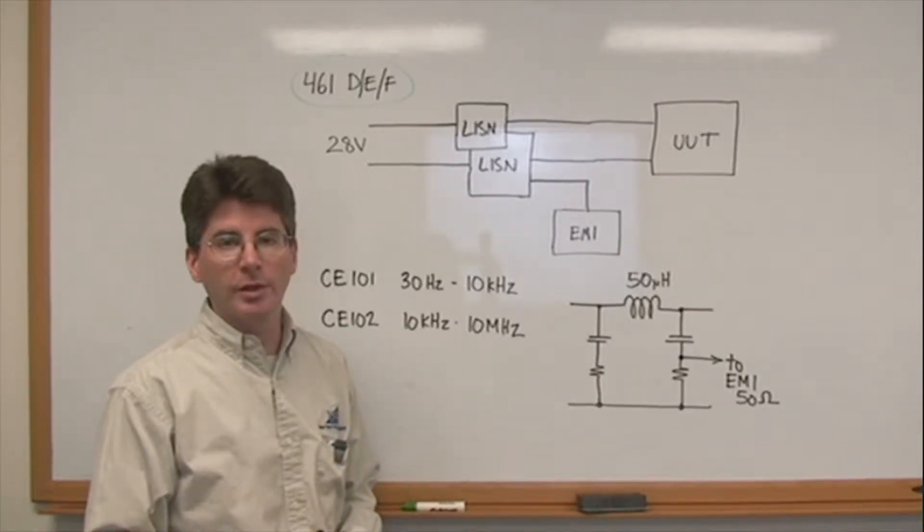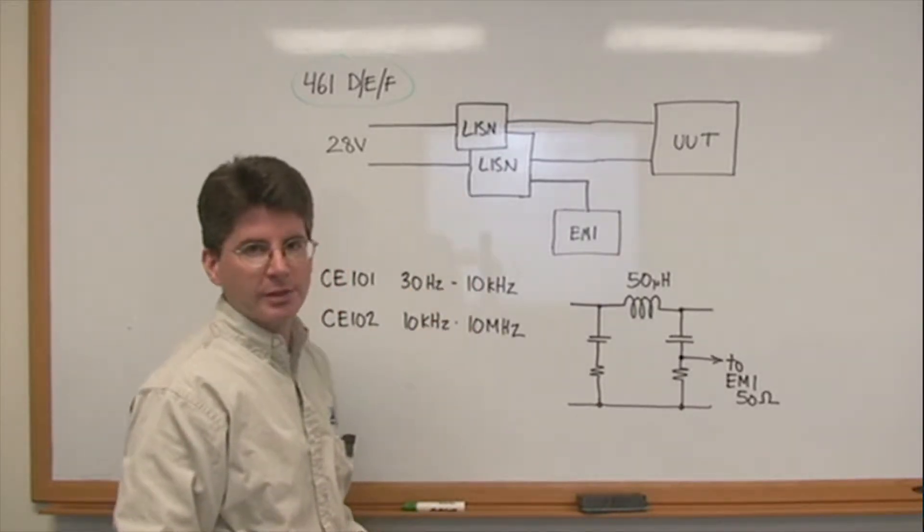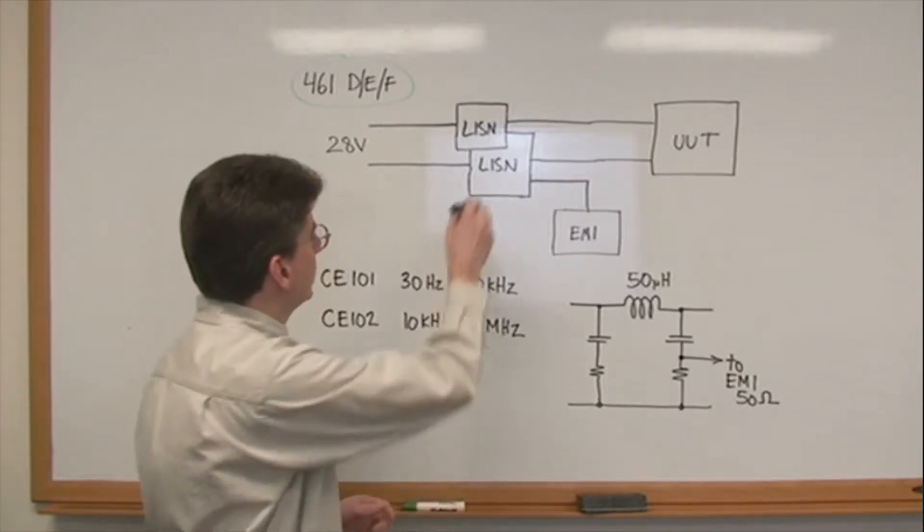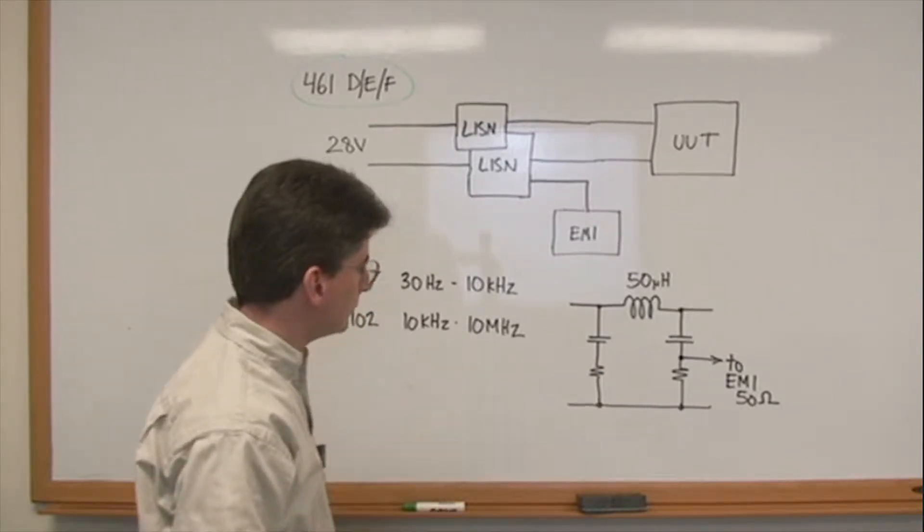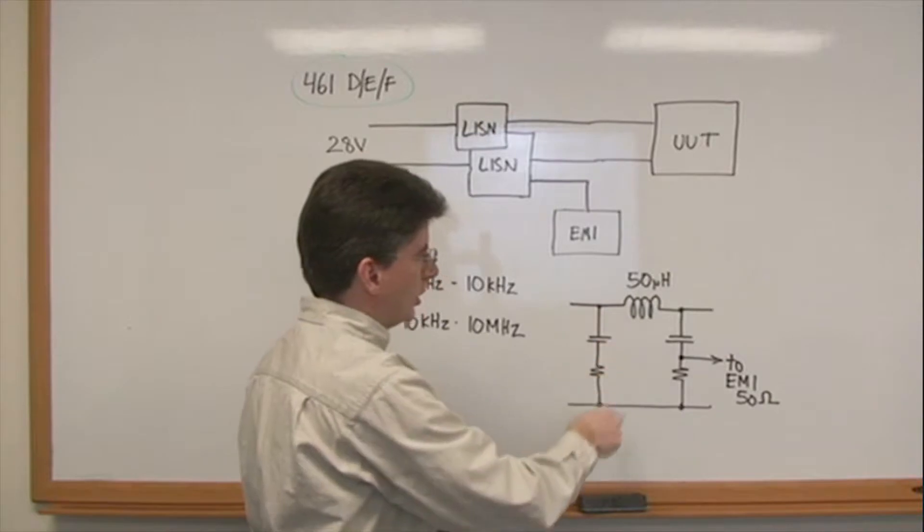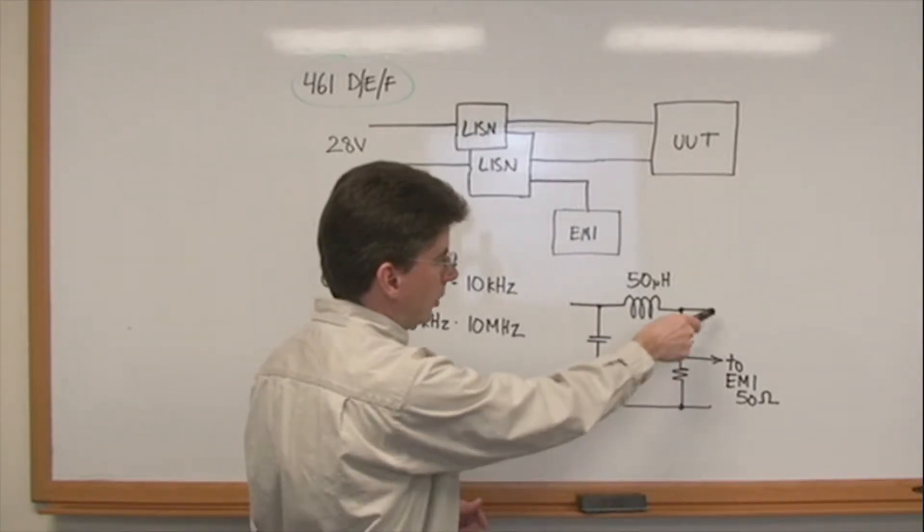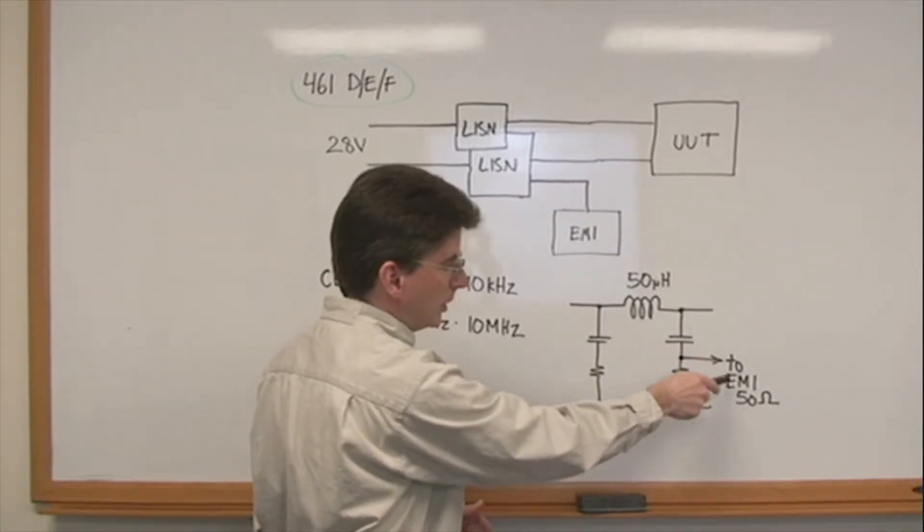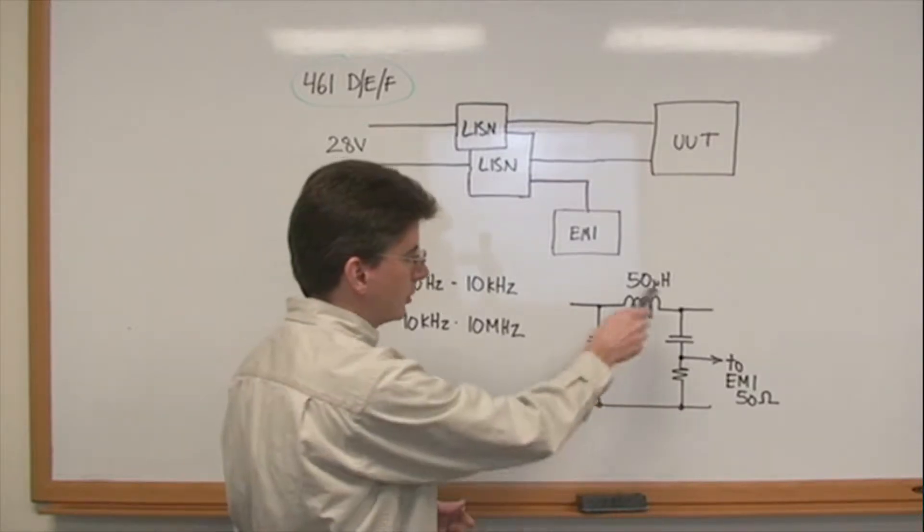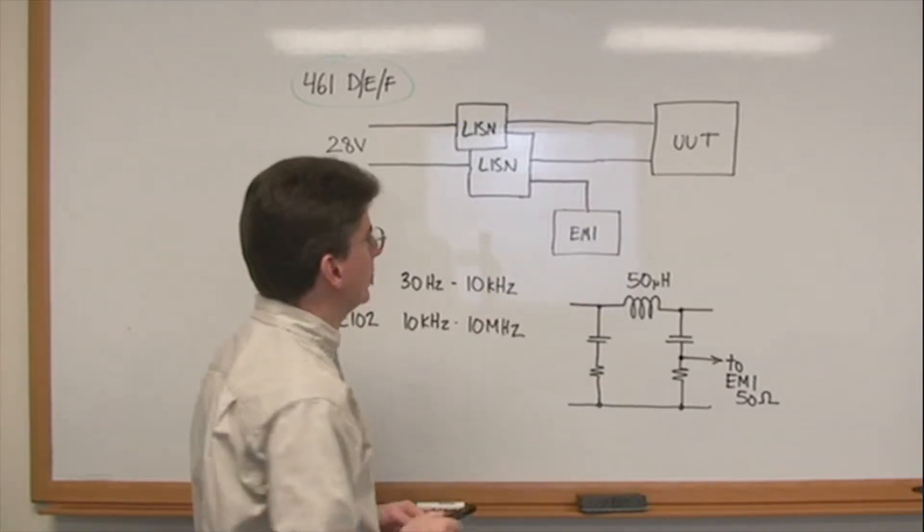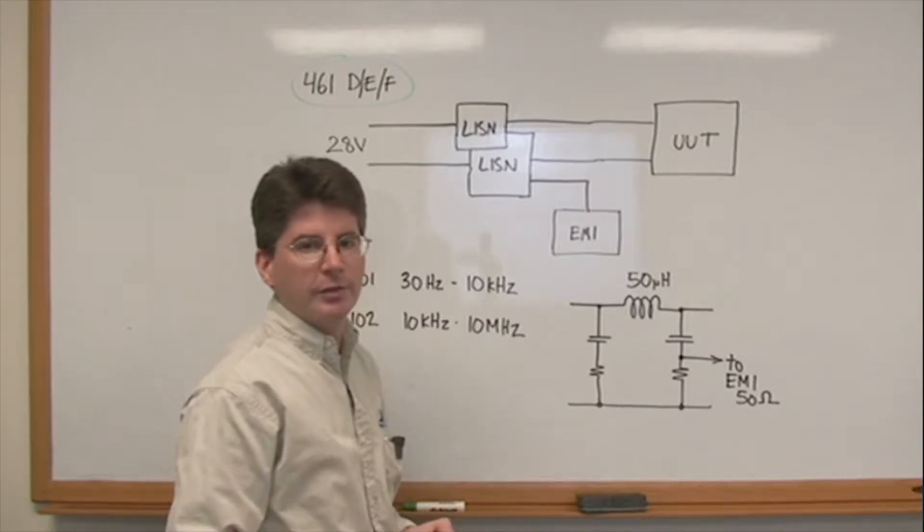This is the setup for MIL-STD-461 revisions D, E and F. This setup uses a LISN or line impedance stabilization network, and the LISN is placed between the 28 volt supply and the unit under test or DC-DC converter. A schematic of the LISN is shown here, but it is basically a large inductor, and on the converter side or the unit under test side there is a capacitor where we plug into the EMI analyzer and we will measure the noise in this manner. So the output of the LISN goes directly to the EMI analyzer. The other LISN on the other line is terminated into 50 ohms.